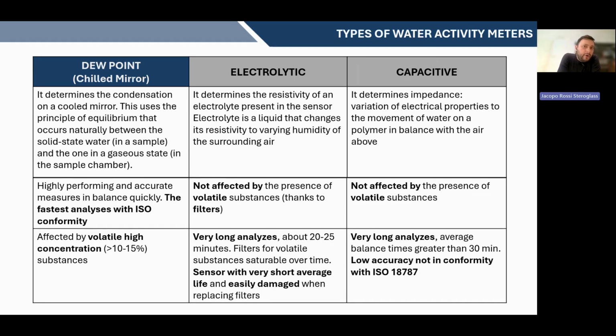As a weak point, it can be affected by volatiles, for example from alcohol or from perfume, if you have them at high concentration, usually higher than 15%. Why? Because here we measure in a closed chamber, so these volatiles go to the chilled mirror and can affect the proper reading.